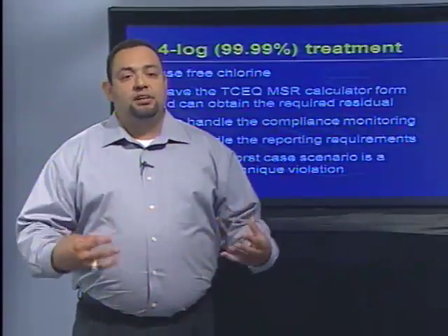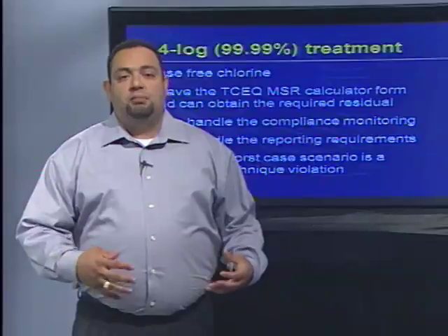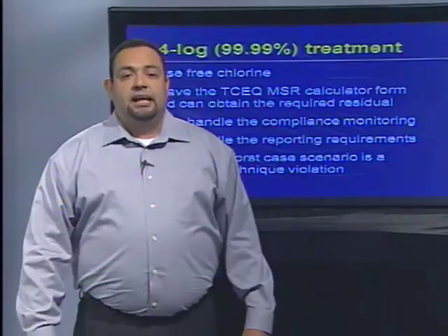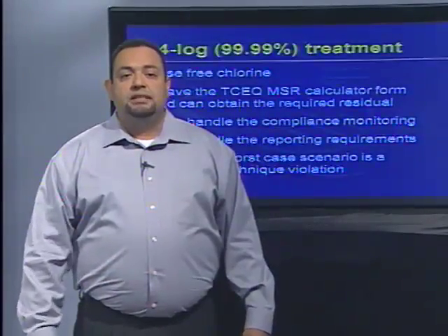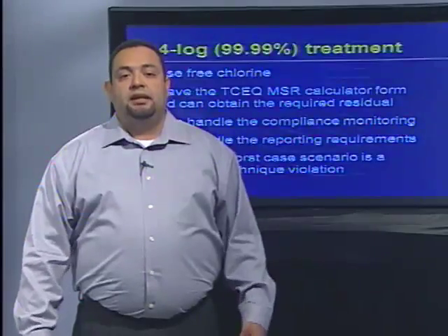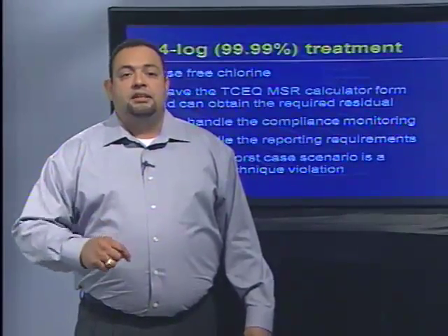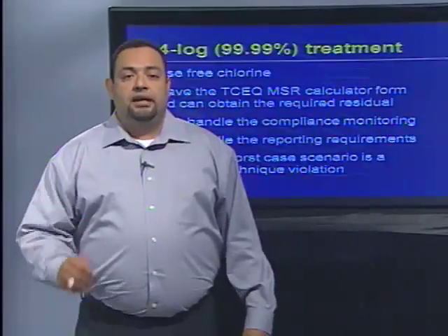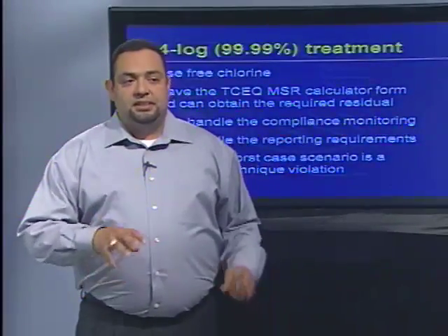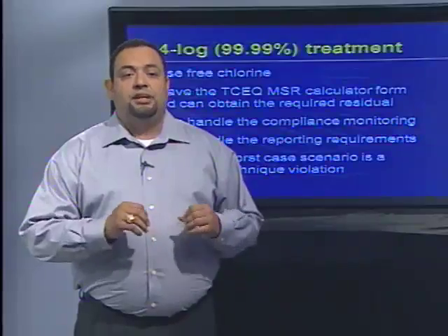So not only do you have to worry about compliance monitoring, you have to worry about reporting and possible public notifications. And then the worst case scenario, if you do fall below the minimum specified residual and you fall below 4-log treatment, you could possibly have a treatment technique violation. And that treatment technique violation, as with all violations typically, requires a public notification. So this is very important with this option that you consider that.